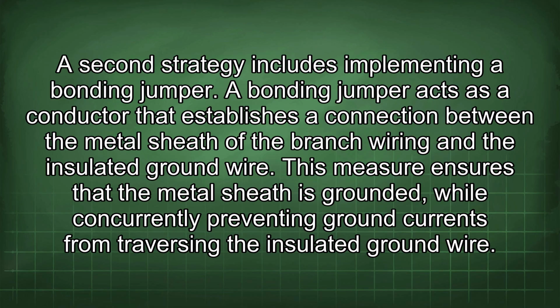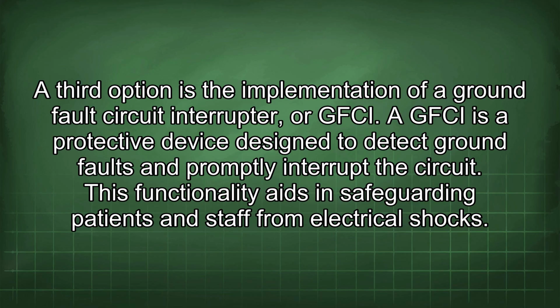A second strategy includes implementing a bonding jumper. A bonding jumper acts as a conductor that establishes a connection between the metal sheath of the branch wiring and the insulated ground wire. This measure ensures that the metal sheath is grounded, while concurrently preventing ground currents from traversing the insulated ground wire. A third option is the implementation of a ground fault circuit interrupter, or GFCI.